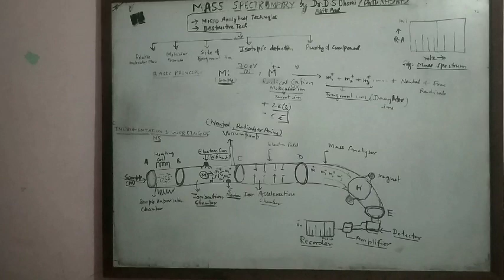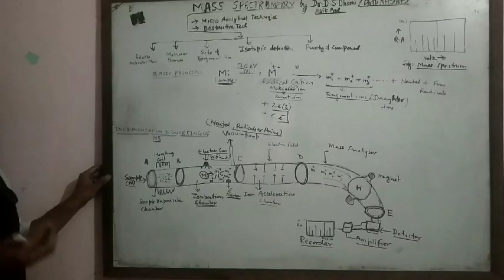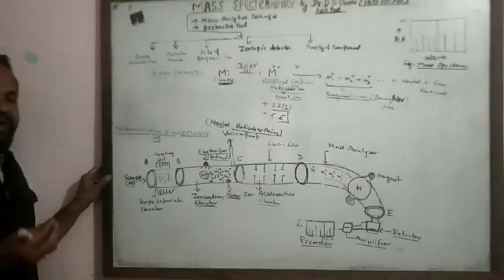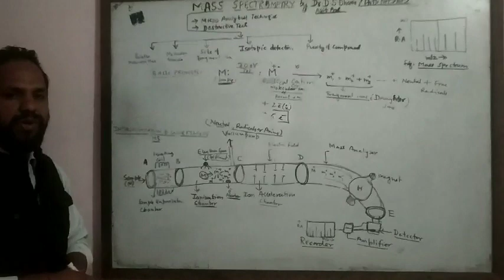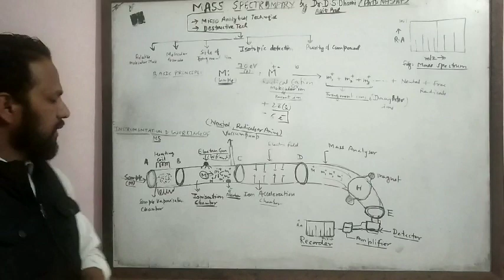Now, the working of mass spectrometry. At first, the sample is introduced from the sample inlet and enters the sample vaporization chamber, where a heating coil is present. If the sample is a gas, then there is no problem, but if the sample is solid or liquid, then it has to be converted into vapor. The vaporization is done with the help of the heating coil.